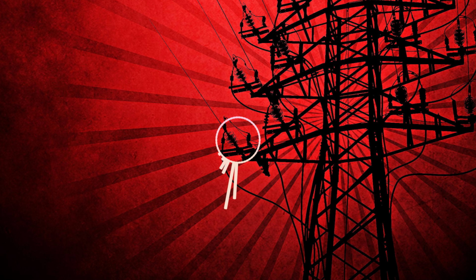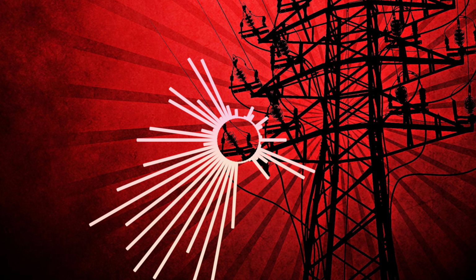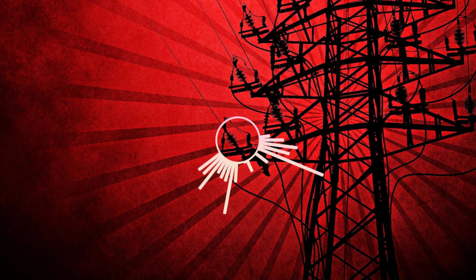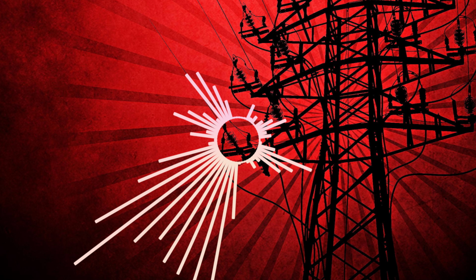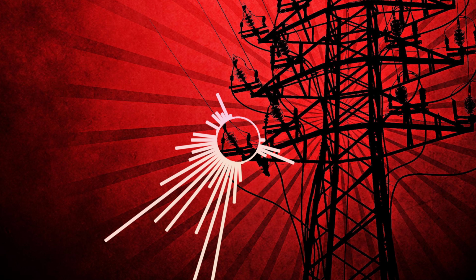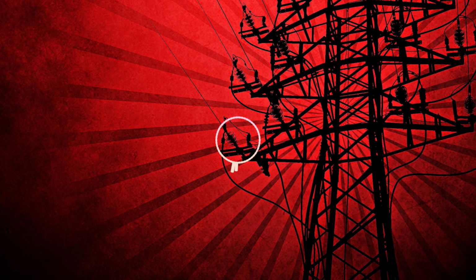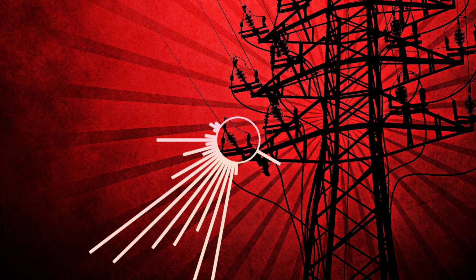Here's the essence of the code: for large electrical equipment, the entrance and exit from the working space must be arranged so that you don't have to squeeze between equipment or walls or risk getting trapped. In other words, when equipment is very big, the NEC requires you to have a clear and direct path in front of it. You shouldn't have to snake your way through gaps or awkward spaces just to get to the gear or leave after working. If equipment is installed side by side, there must be enough space between them so that workers can move freely and safely.